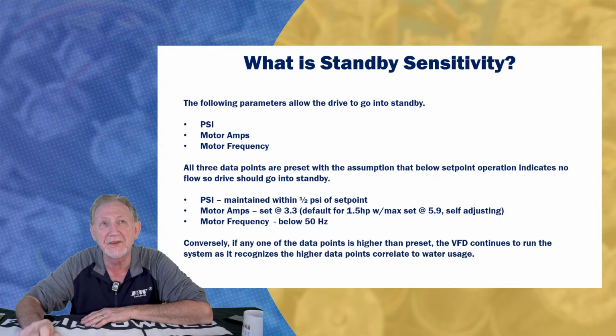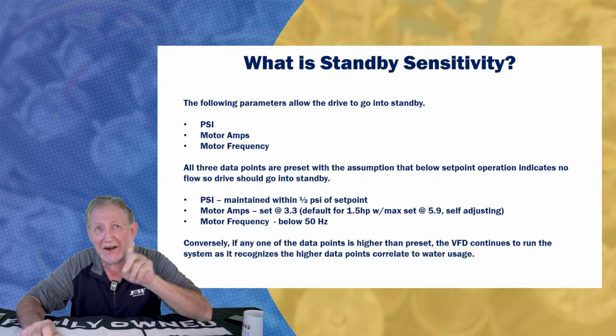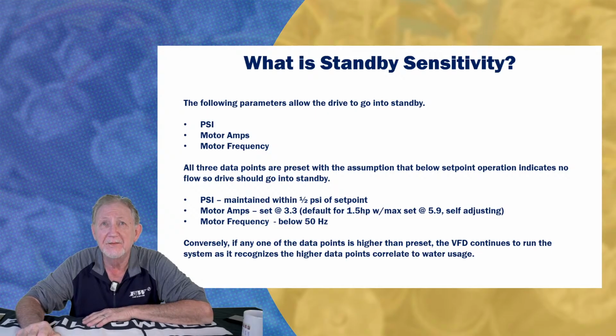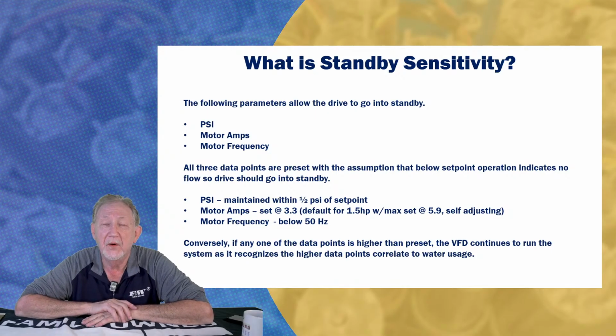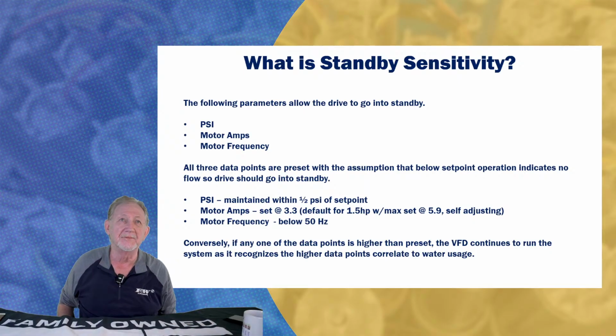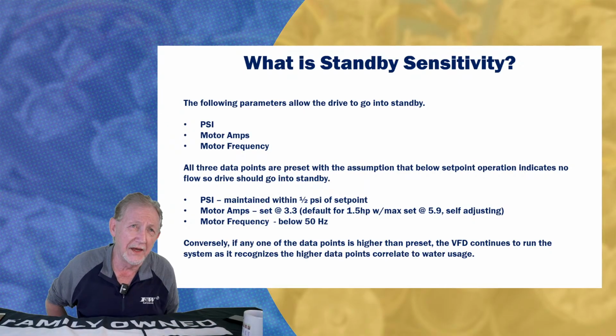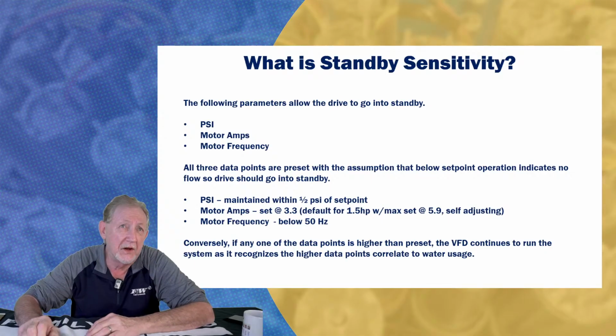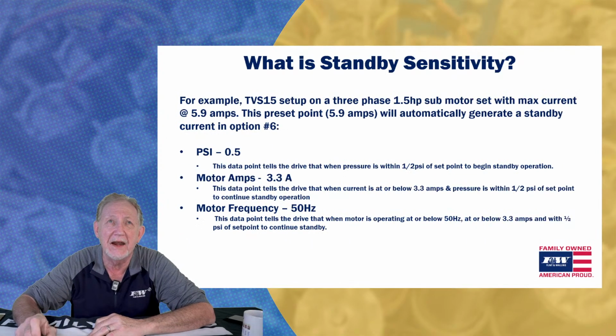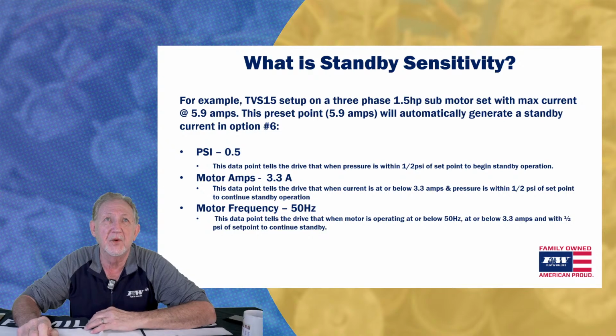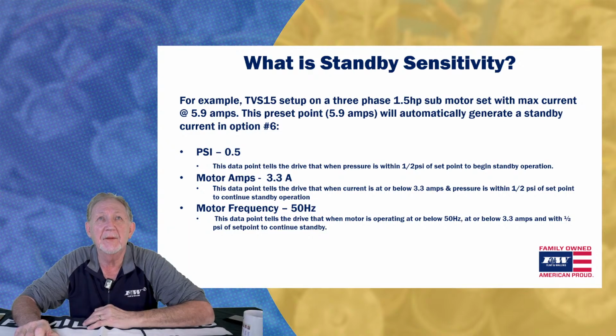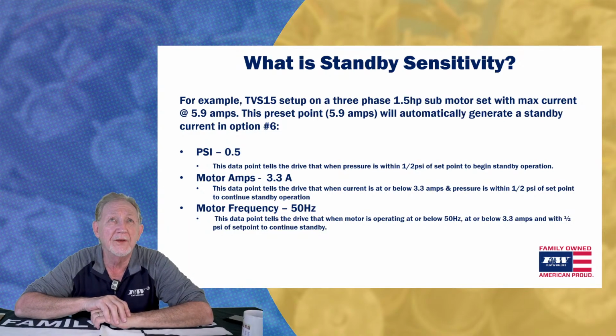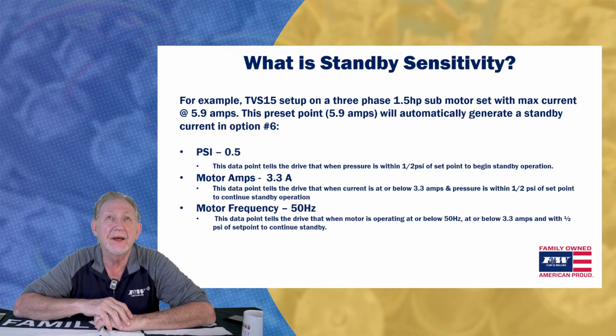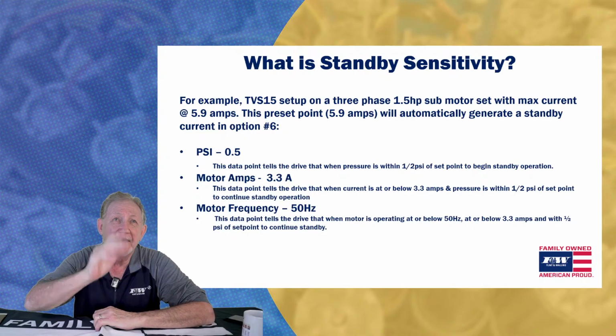But anyway, conversely, if any one of these data points is higher than that preset, well then what happens is that VFD is going to continue to run, and it's going to correlate that as there's water being used. Again, if it's running higher than that set point. So here's another example of standby sensitivity.